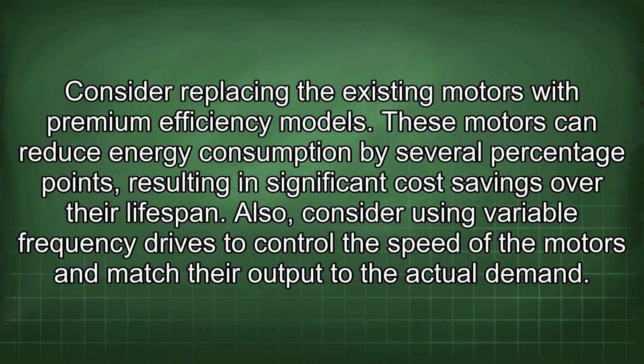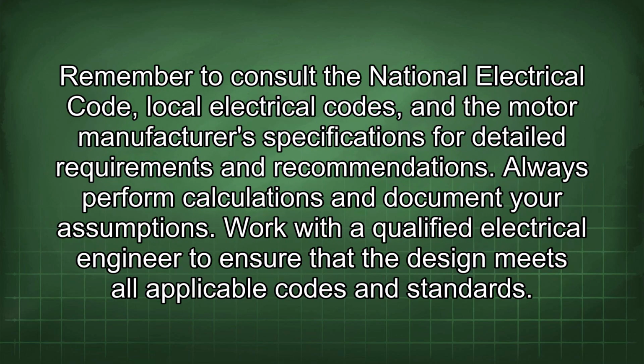Also, consider using variable frequency drives to control the speed of the motors and match their output to the actual demand. Remember to consult the National Electrical Code, local electrical codes, and the motor manufacturer specifications for detailed requirements and recommendations. Always perform calculations and document your assumptions. Work with a qualified electrical engineer to ensure that the design meets all applicable codes and standards.